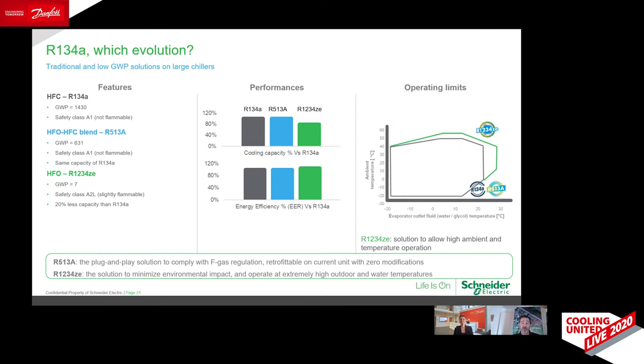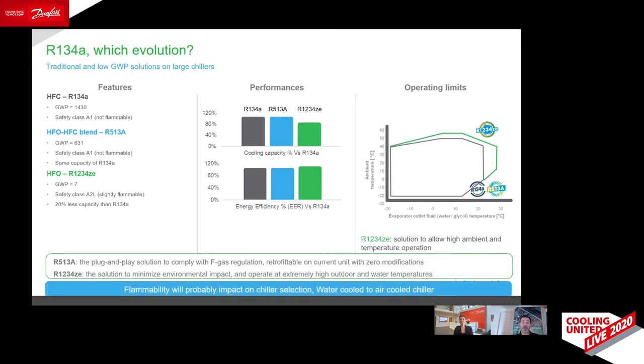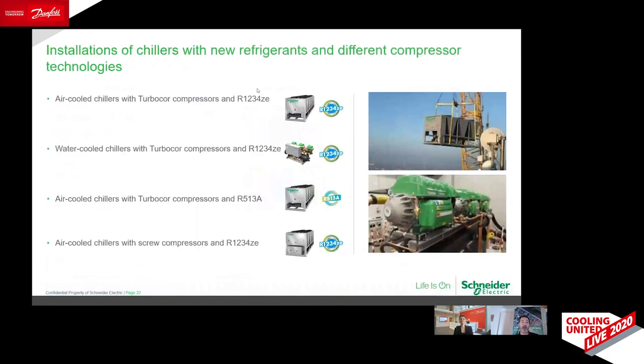Are you looking for low GWP? The choice is certainly the 1234ZE, which is characterized by lower capacity. The best compromise is the 513, which is not flammable. But if you are looking at the air-cooled chiller, probably flammability is not a problem anymore. So let's say that we need to have an overall choice. Schneider is able to provide all the chillers for you, all the solutions for you, with the refrigerants available, with Turbocor, screw or scroll compressors, to comply with your request.